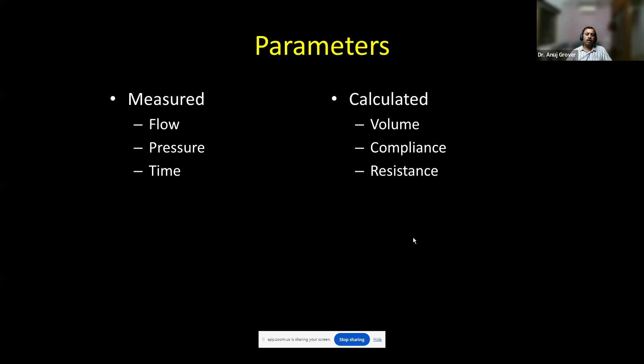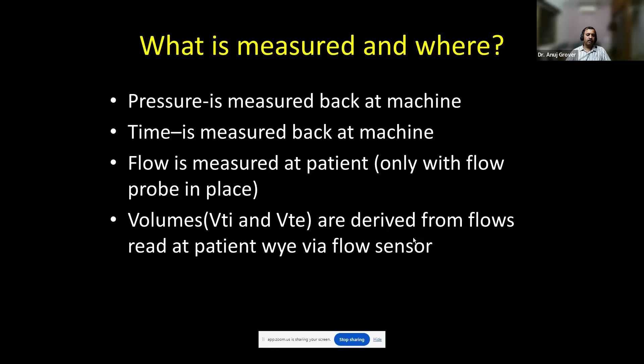So what is measured where? So the pressure is measured at the machine end, the time is measured at the machine end, the flow is measured at the patient end with the flow sensor in place. Okay. Based on the flow, the volumes are then calculated using an algorithm.